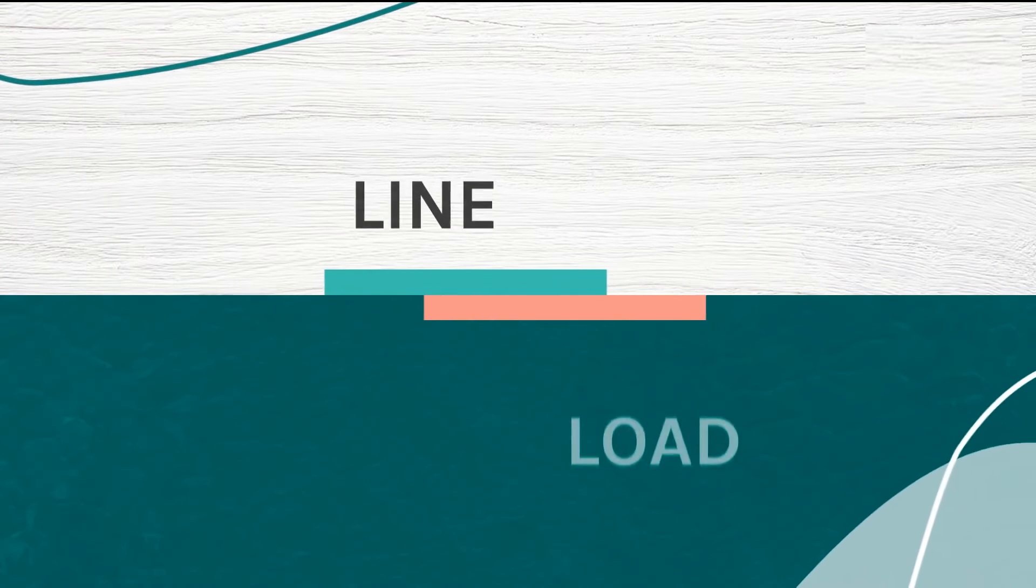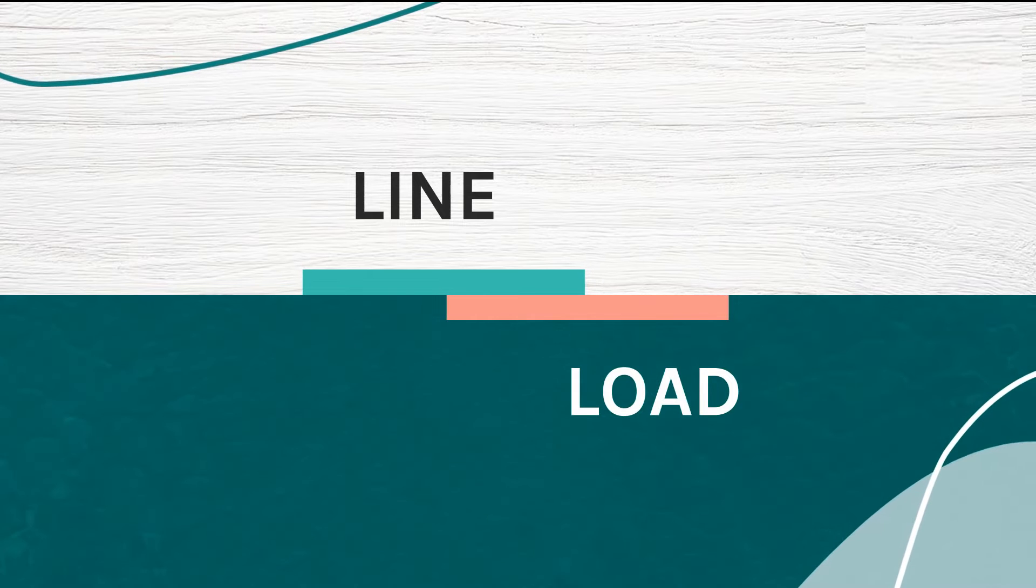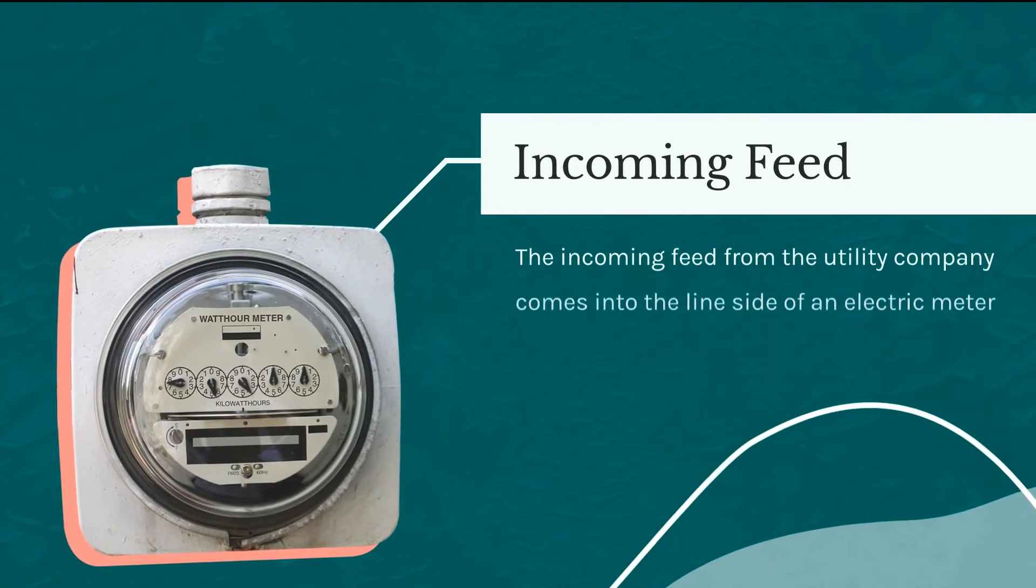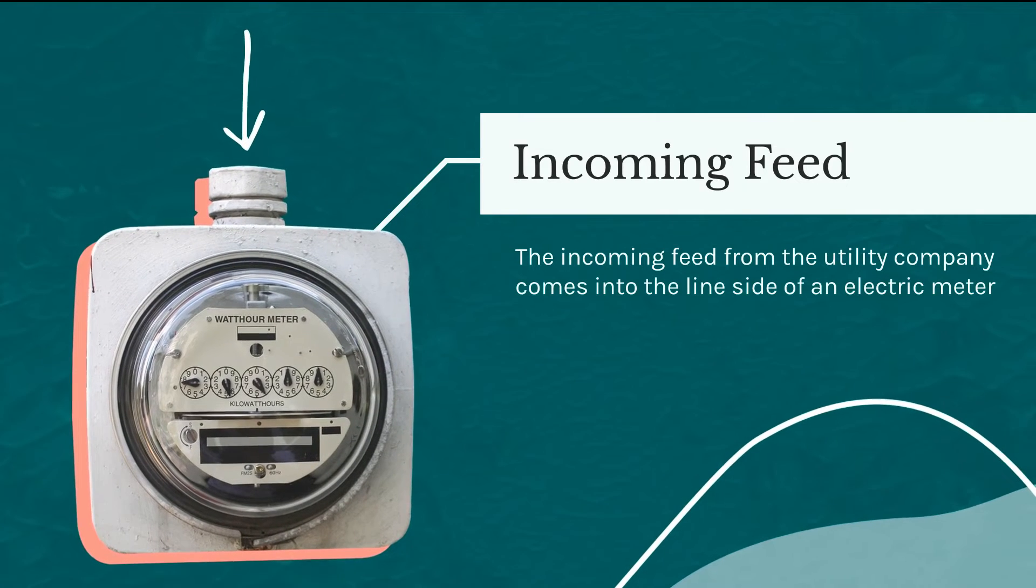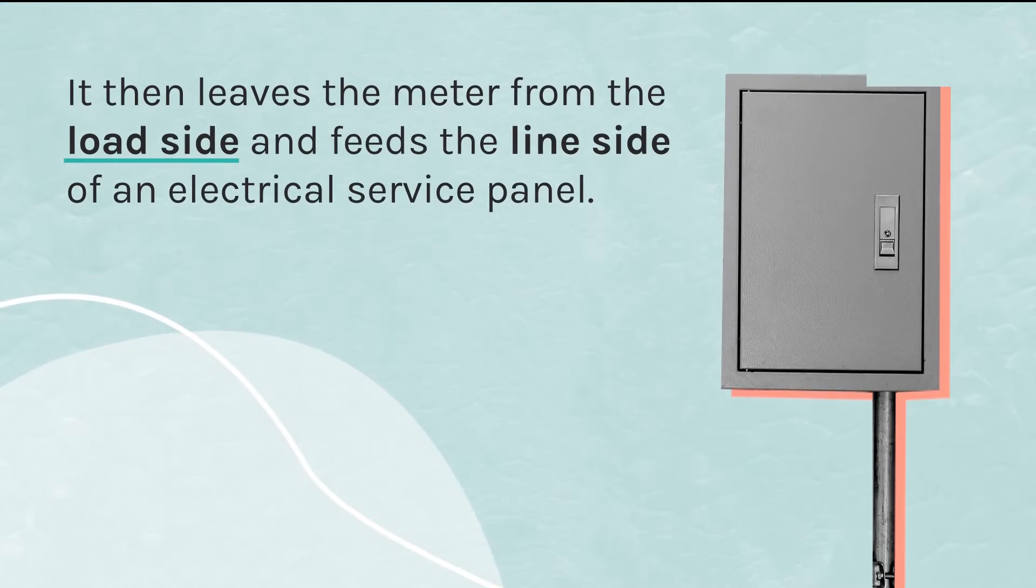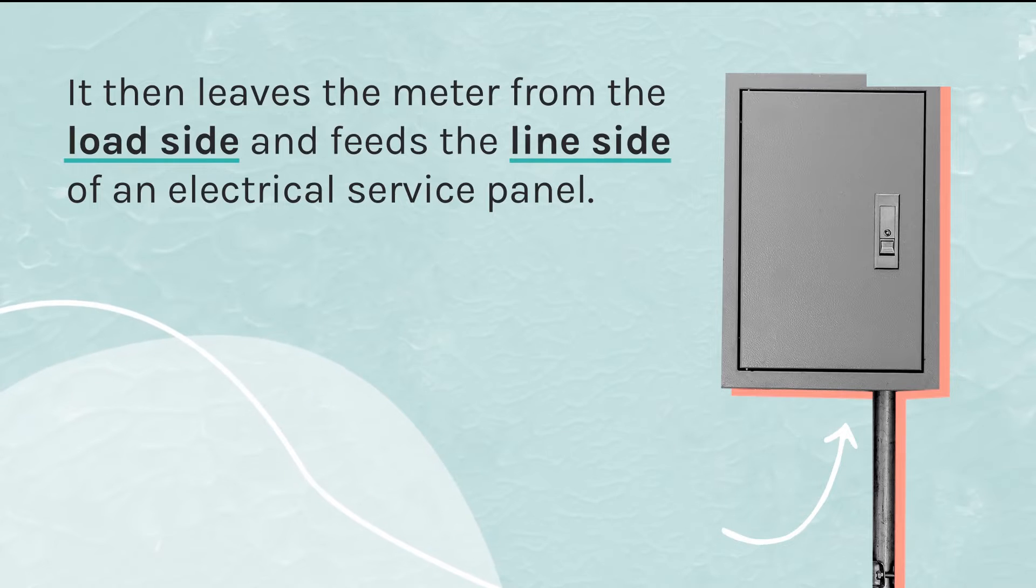The terms line and load have a number of applications at different locations in an electrical system. The incoming feed from the utility company comes into the line side of an electric meter. It then leaves the meter from the load side and feeds the line side of an electrical service panel.